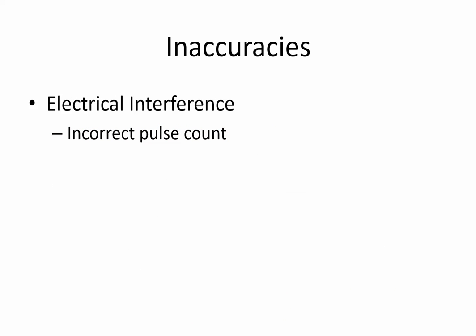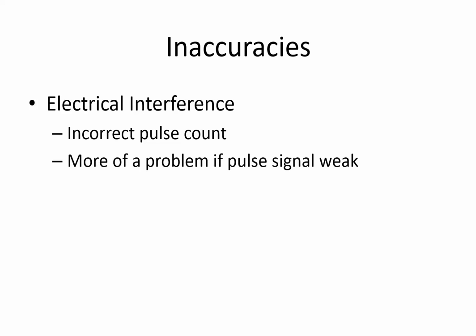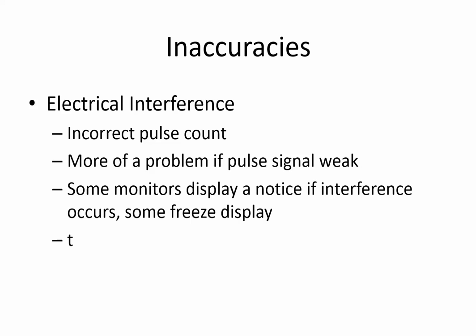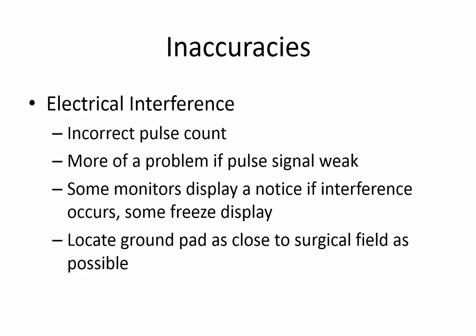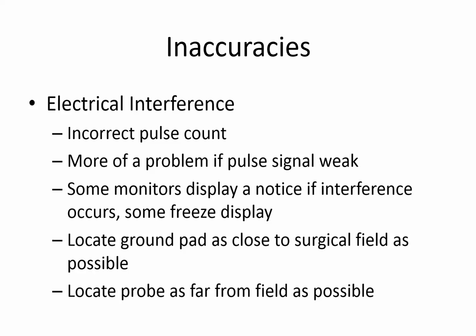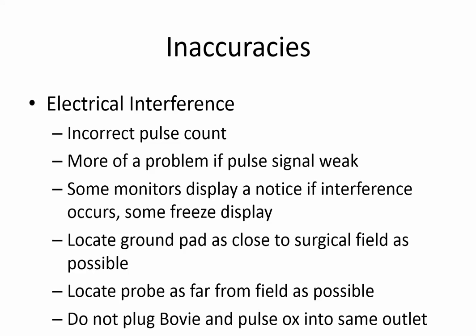Electrical interference generally causes an incorrect pulse count. It's more of a problem if the pulse signal is weak. Some monitors display a notice if the interference occurs, some freeze the display. Things to do to try to minimize this problem are to locate the ground pad as close to the surgical field as possible and locate the pulse oximeter probe as far from the surgical field as possible. Also, don't plug the bovie and the pulse oximeter into the same circuit.